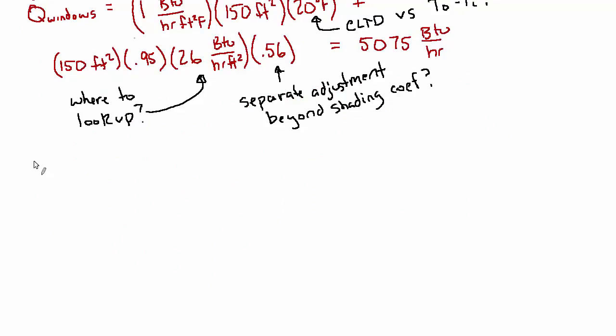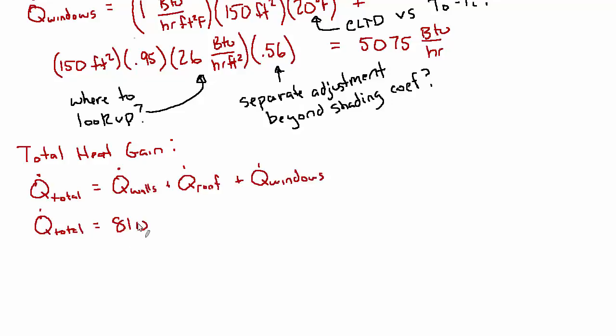Okay, so let's now go for the total heat gain. The total heat gain will be the sum of the walls, roof, and windows. We're neglecting the floor. And the values we found were 8,107 BTUs per hour, 10,212, and most recently for the windows, 5075. Which gives a total of 23,394 BTU per hour. And that is the answer to part A.